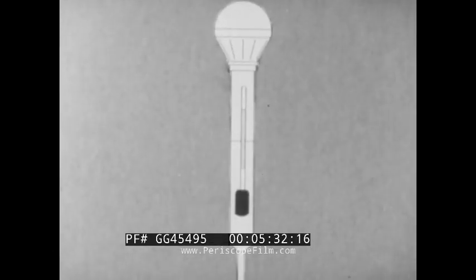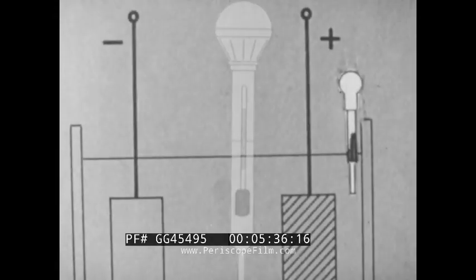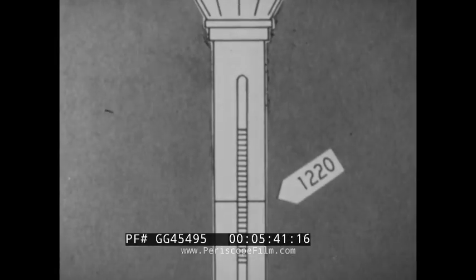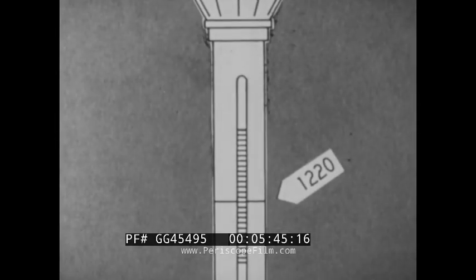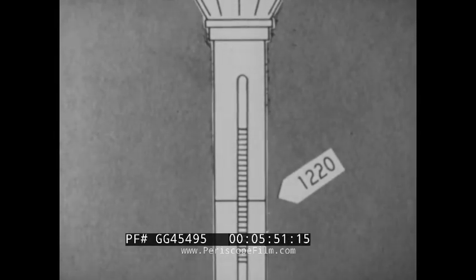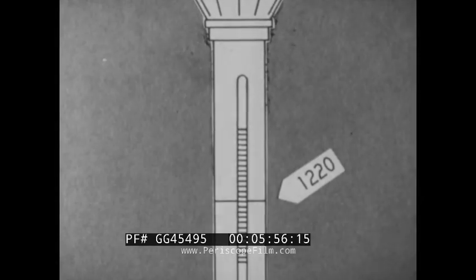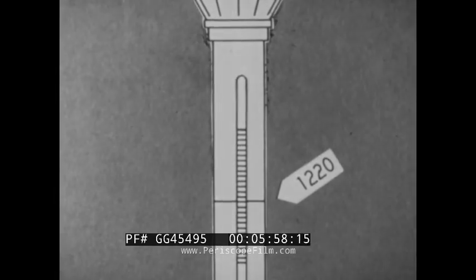The charge condition is indicated by the weight of the solution as measured by a hydrometer. The hydrometer measures the specific gravity or weight of the electrolyte as compared to the weight of pure water. Most telephone batteries are designed so that the specific gravity at full charge is about 1.22, commonly known as 1220.